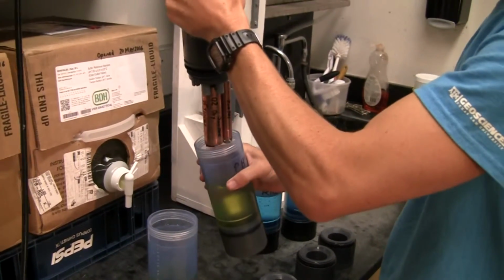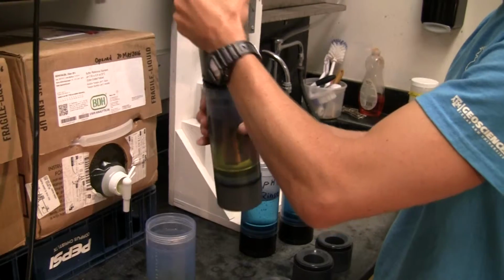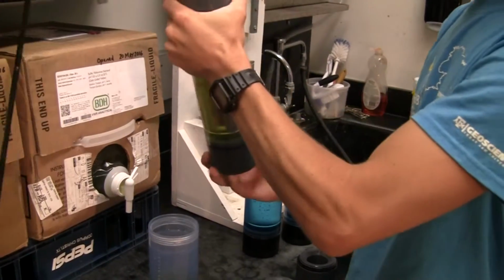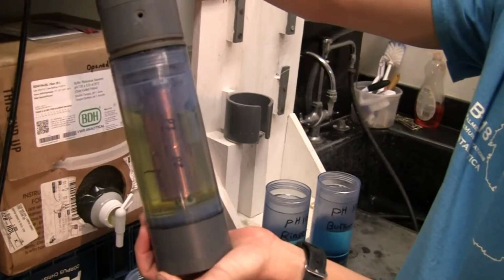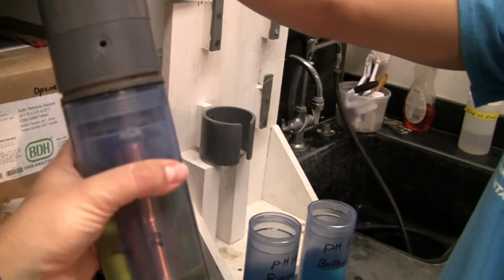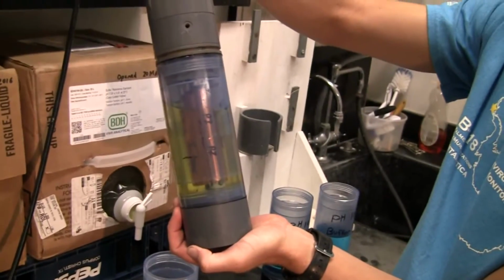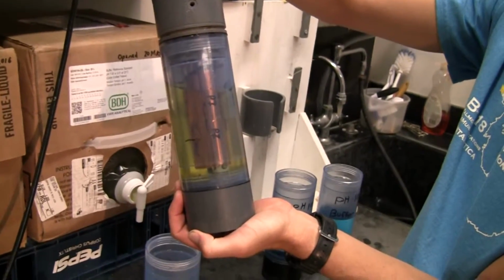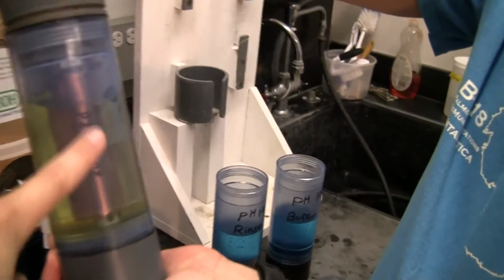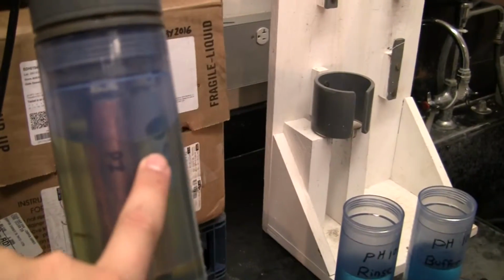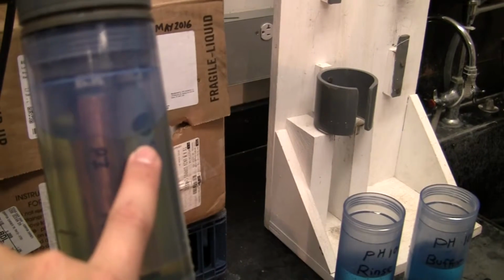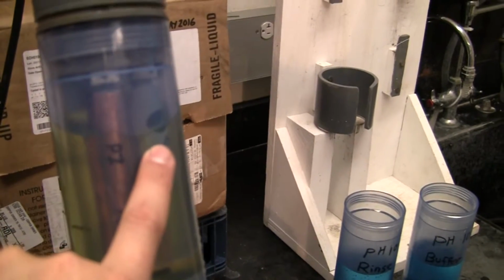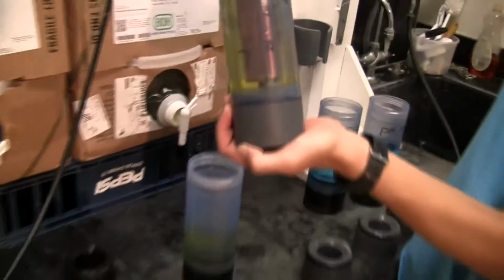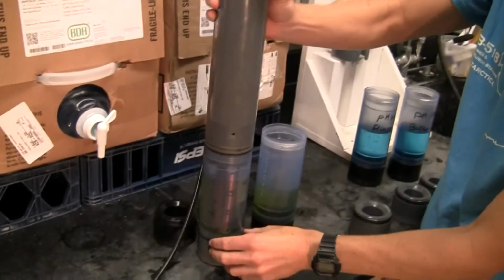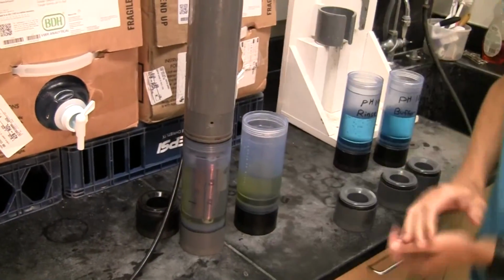And now placed into the buffer solution. So now we make sure that the top was screwed in tightly, but this sensor we do not put upside down. So we leave it right side up, so that way the solution can fully cover the salinity sensor, which is also the temperature sensor, because we need that for calibration purposes. And we set it straight down on the table, and we move to the computer.